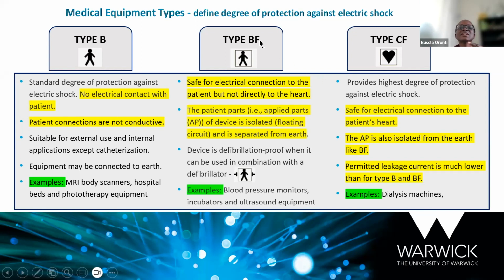Secondly, the second type of medical devices we have is the BF. And this is safe for electrical connections with the patient, but there will be no direct connection to the heart. So the applied parts of the device are isolated. So there is no connection between the floating parts of the device and the earth. Examples of this are blood pressure monitors, incubators, ultrasound equipment.